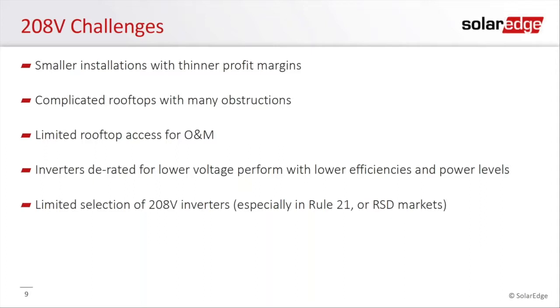208 inverters in general in the industry tend to be 480 volt inverters that have been derated for 208 operation. What that means is you're getting essentially the same current inverter, able to handle X amount of current in both cases. But in one case, you're selling that product as a 480 volt solution, and in the other case, as a 208 volt solution. So you're seeing the power drop by more than half for very similar technologies applied to a 208 volt installation. That comes with some trade-offs. We get, in general, lower efficiencies for these types of products and lower power levels. For legacy products, that's definitely true. We're going to introduce a product today that changes that.